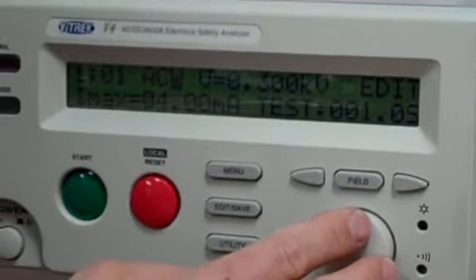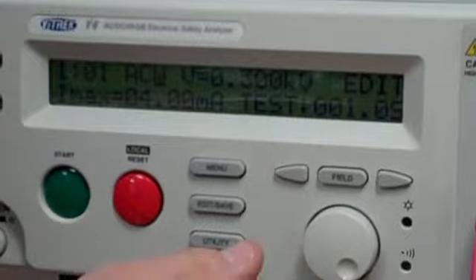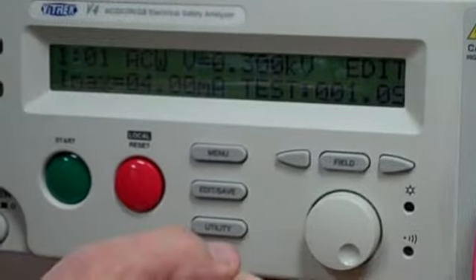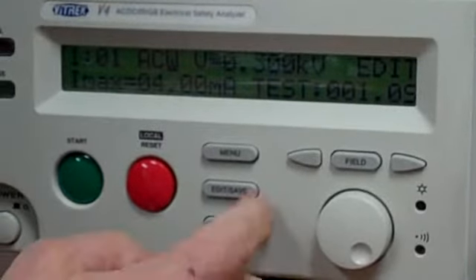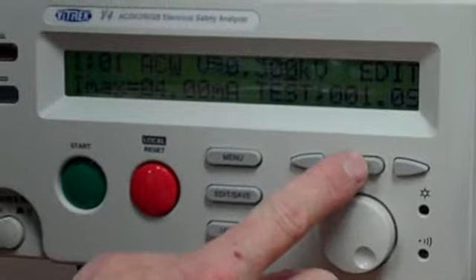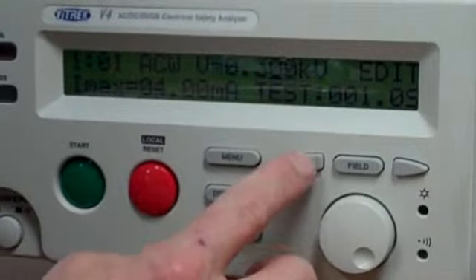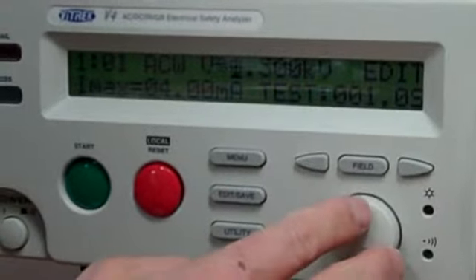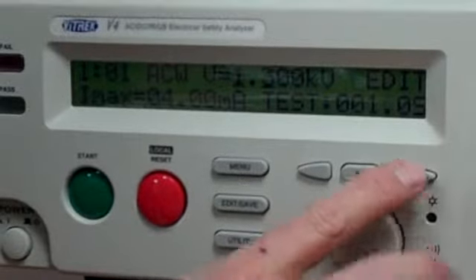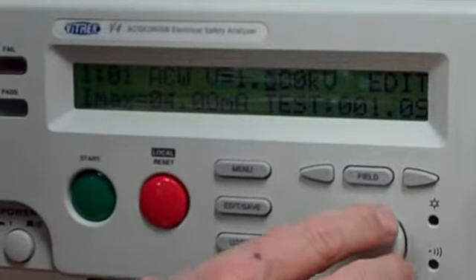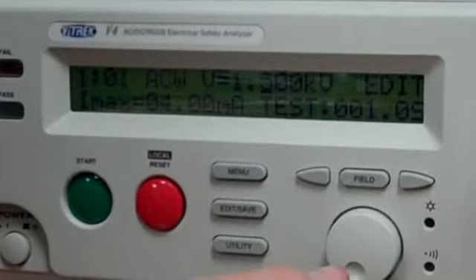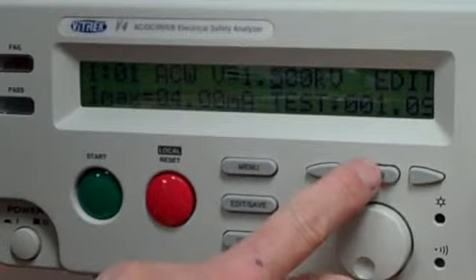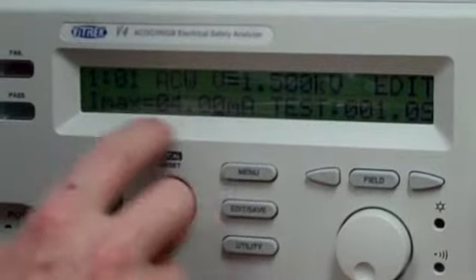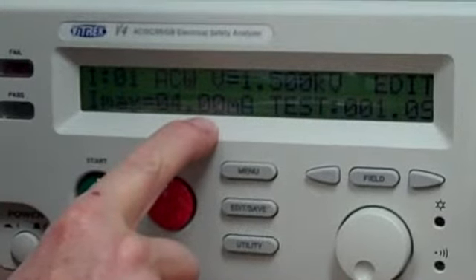So for my first function, I could do an AC high pot test, which is AC voltage withstand test, and then use the field button to go over here and set the output voltage. We're going to do a 1500 volt test today, a pretty popular test for UL. Set the voltage at 1.5 kV, advance to the current field. Now the cursor is under the current level.